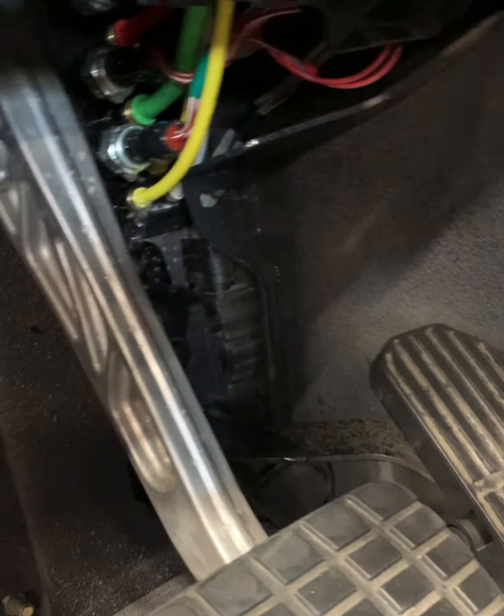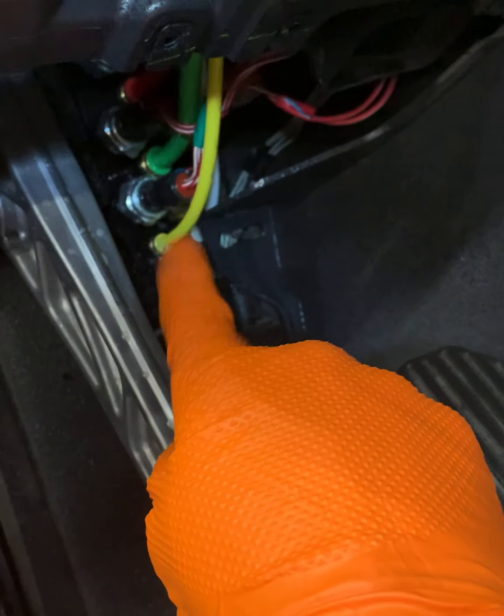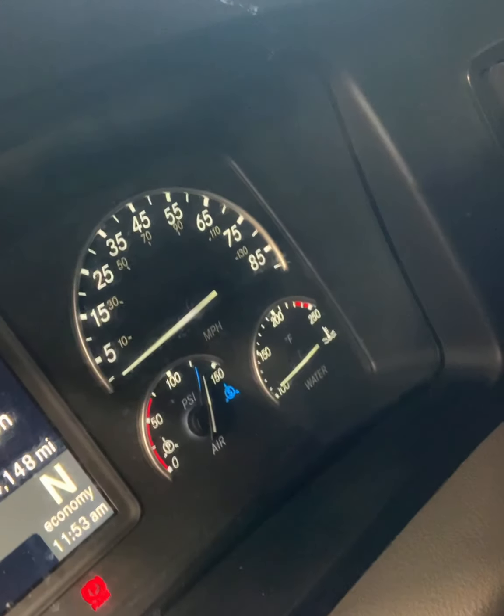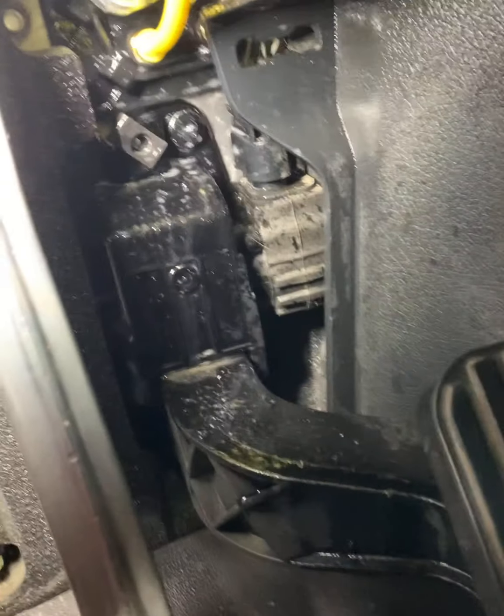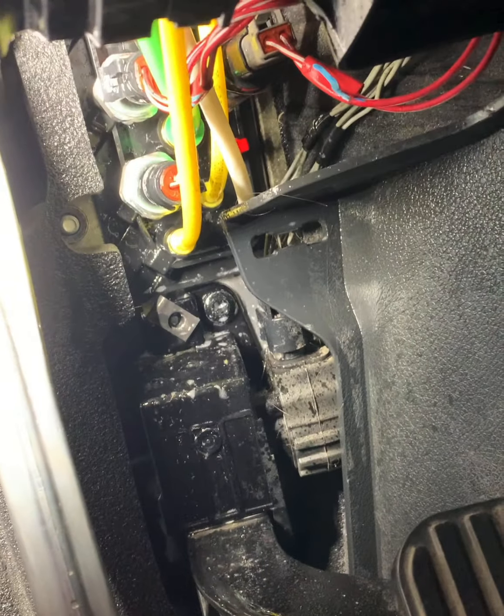And you know what? There's a leak right there. See, it's a good thing we did it. If we just trusted ourselves, we would have failed. So we're gonna go ahead and fix that leak. We're gonna go ahead and repressure it up and check again. You don't wanna screw this up now. Every job's gotta be done right. Looking good, looking good. All right.